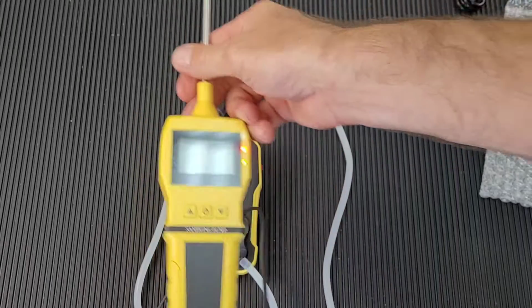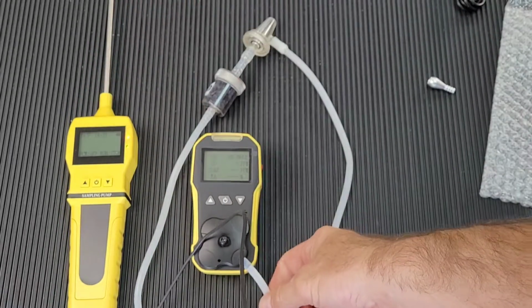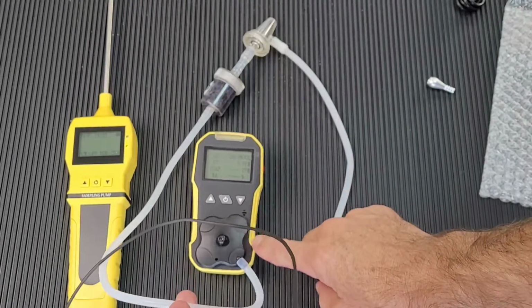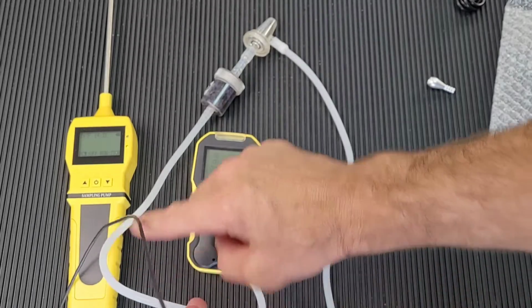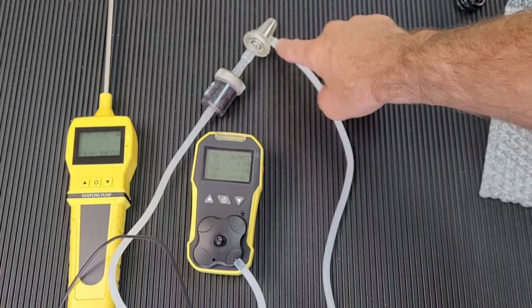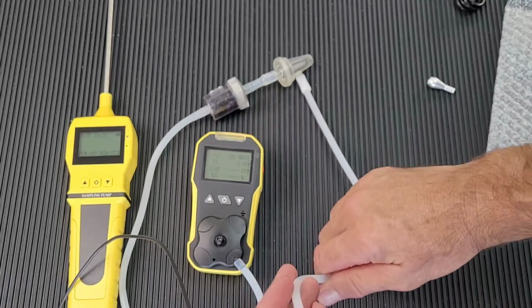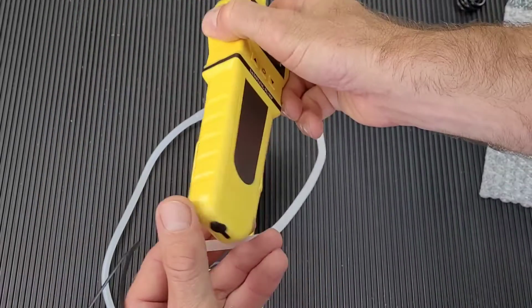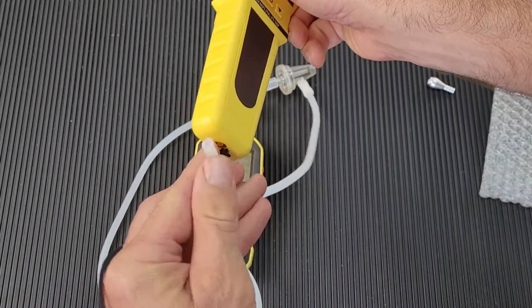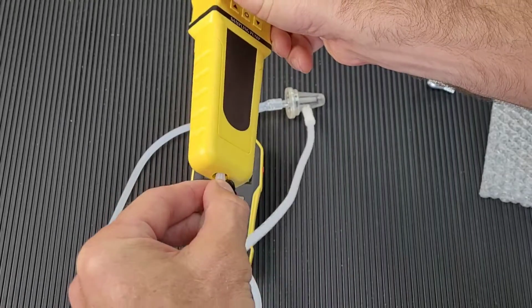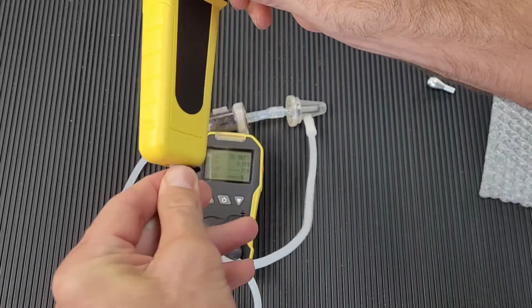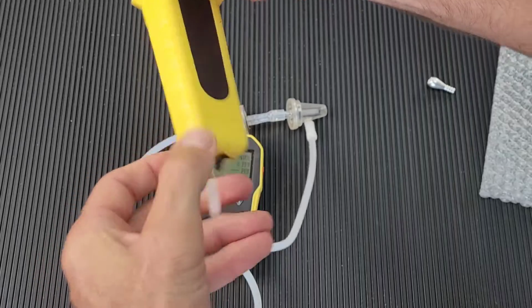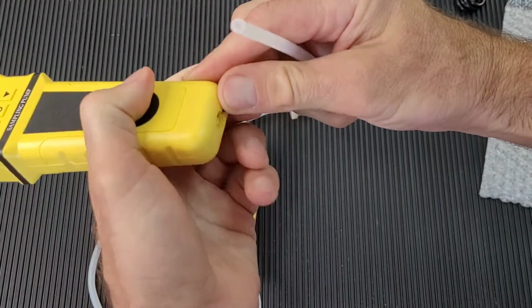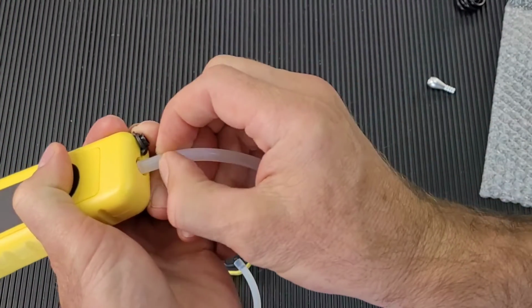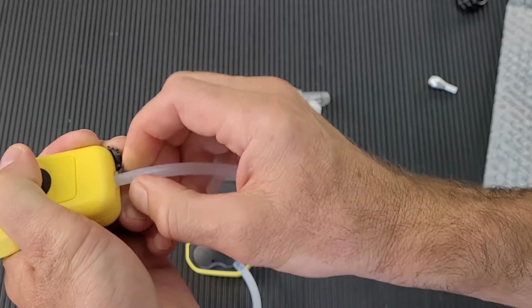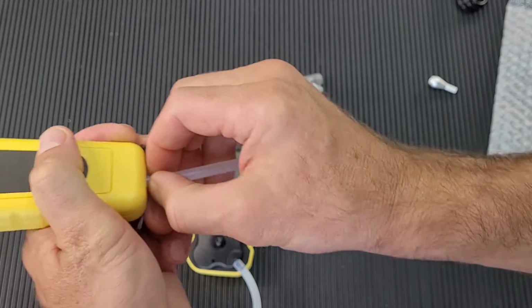Okay, so that's the pump. Then we have it. So let's go back to the analyzer. We have the cap on with the screw. It goes through the filter, water trap, and then we want to put it at the bottom of the pump. Okay, and that's basically it. And it's very important, folks, not to rush this. I'm rushing because I've got a bit of a video going on here, but when you're doing it, make sure all your connections are very tight. And I have to do that now because we're going to test this guy. You're going to see it running.